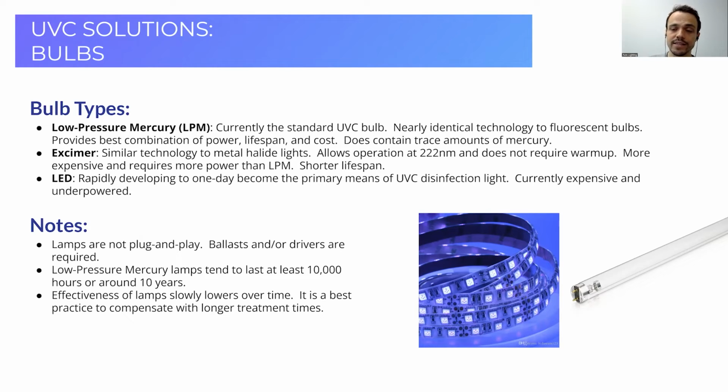And then finally, LED. LED, as we know from our standard illumination, is the holy grail. We get all sorts of form with that. We have all sorts of flexibility. We have insane efficacy. We have insanely long lifespans. We have high quality light that's output. Right now, UV LED isn't quite there. It's getting better. It seems every week, every month, a new advance has been taken, but they still haven't found the proper combination of metals and minerals to emit UV light at a dosage, at an efficacy, and at a lifespan that makes sense. Right now, to get an equivalent to a low pressure mercury lamp is going to be a radically high price. And the heat dissipation will be an issue as well. So certain applications, LED is going to be proper. But for mass deployment, it's almost there, but it's not quite there.